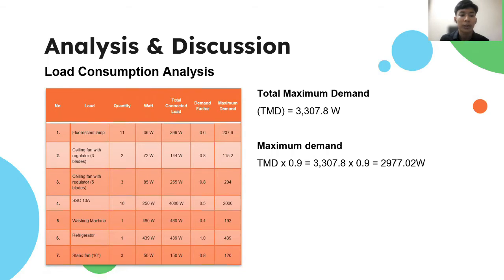For the load consumption analysis before, as you can see in the table here, we have 7 electrical appliances, which consist of fluorescent lamp, ceiling fan of 2 types, which are 3 blades and 5 blades, switch socket outlet 13 ampere, washing machine, refrigerator, and stand fan 16 inches. When we calculate, the total maximum demand is 3,307.8 watt. For the maximum demand, we multiply the total maximum demand with the coincident factor, which is 0.9, to get 2,977.02 watt.